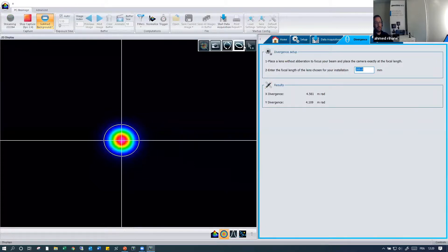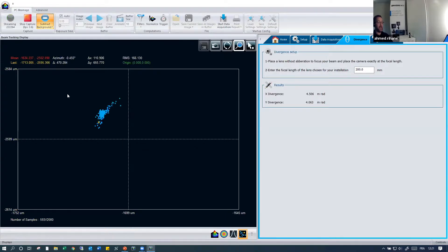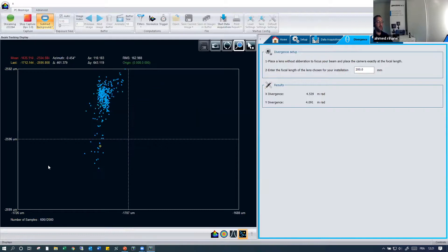Now we talked about beam tracking. In the beam tracking display, you can track your beam and visualize it by zooming in, getting an idea of the stability of the beam. In some applications, it's important to understand how the beam is moving around its mean position.